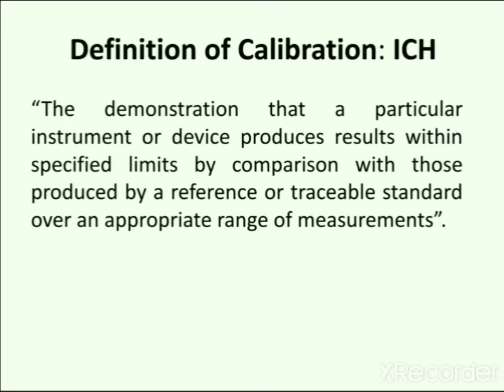So according to ICH, calibration is the demonstration that a particular instrument or device produces results within specified limits by comparison with those produced by a reference or traceable standard over an appropriate range of measurements. This definition states that according to ICH, calibration is the demonstration of whether a particular instrument or device produces results within the specified limits or not. Also, the data obtained is verified by comparison with the data from a reference standard within an appropriate range of measurements.